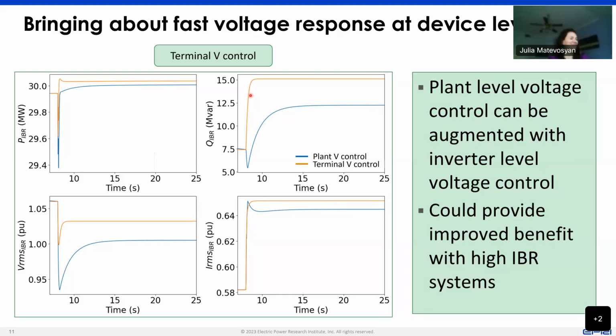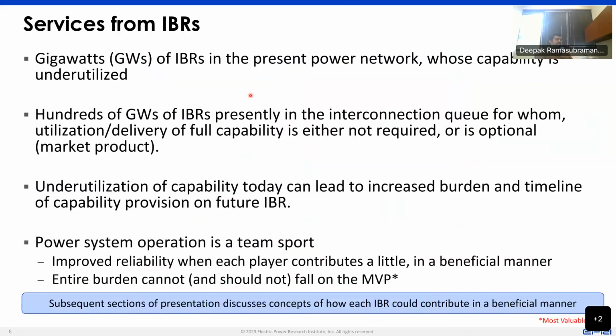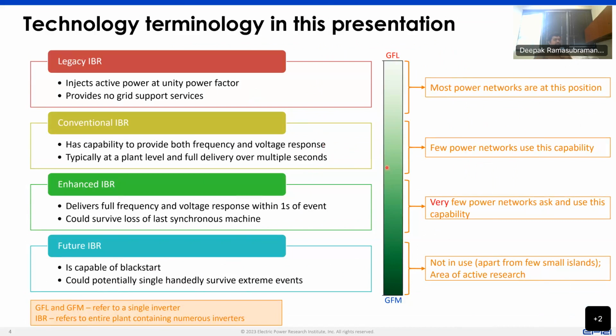Thanks for being concise. The next question is an interesting one. Where does IEEE 2800 fall on the presented transition from grid following to grid forming? That's a nice question. So I would say that in our experience, IEEE 2800 falls anywhere from this point here all the way to maybe this point here, because IEEE 2800 doesn't talk about black start. It doesn't ask black start to be a minimum capability or a technical minimum requirement. One should realize that IEEE 2800 is actually a whole set of different functionality that can be leveraged and utilized. Depending upon how much functionality of the standard is adopted, it can fall anywhere from between here to around about here.